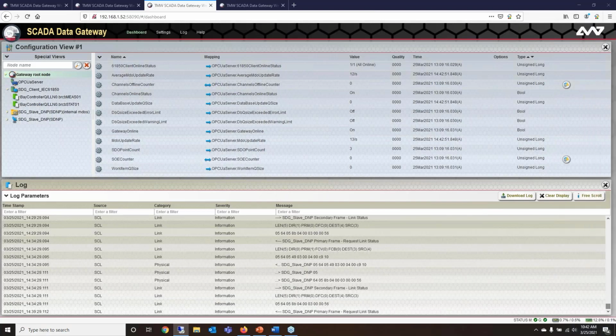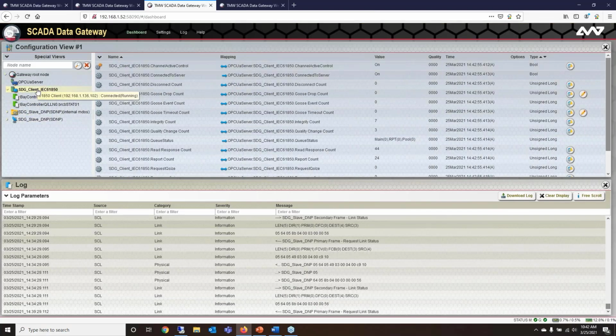So let's look at how we do that in our SCADA Data Gateway. I've got our 61850 client here, and what I'm going to do is add a report control block. I just right click here, and then we simply have add 61850 report control block. When you add these, it automatically enables those reportings on your server, setting up the ability for it to auto send those messages.